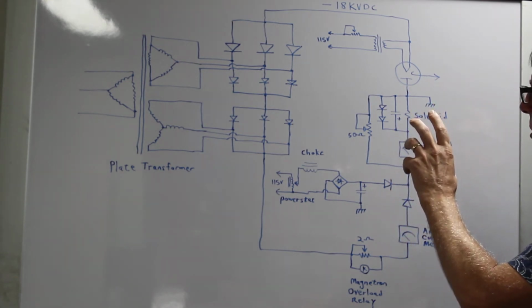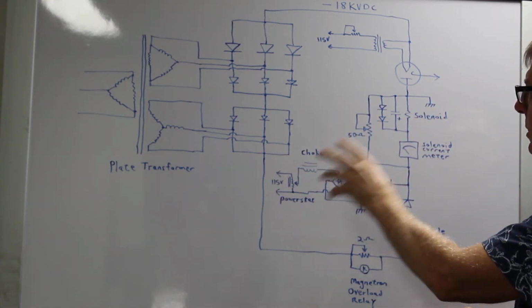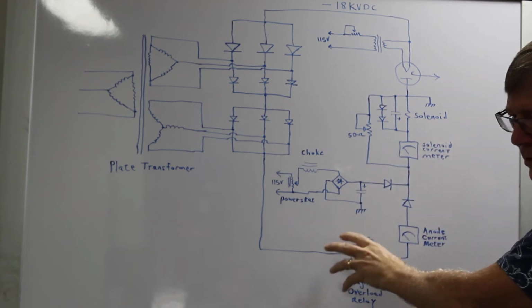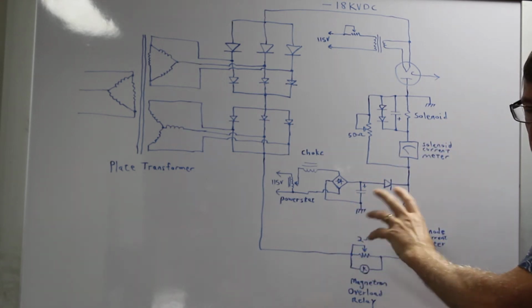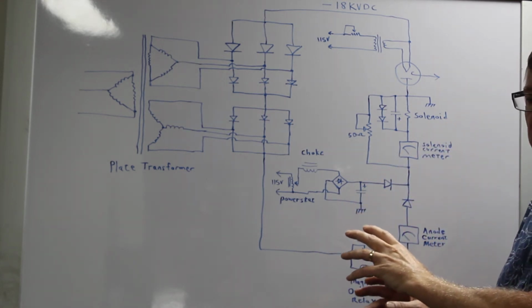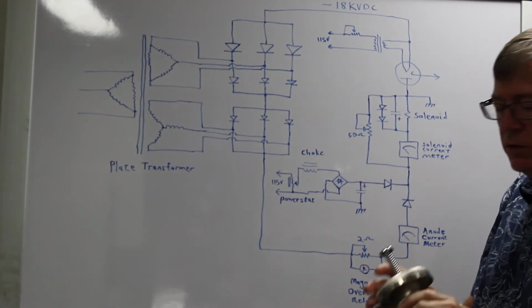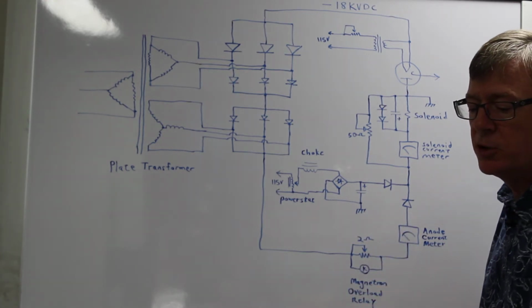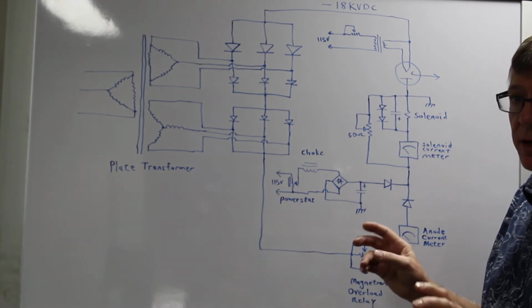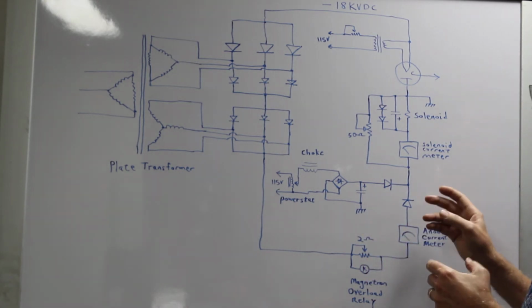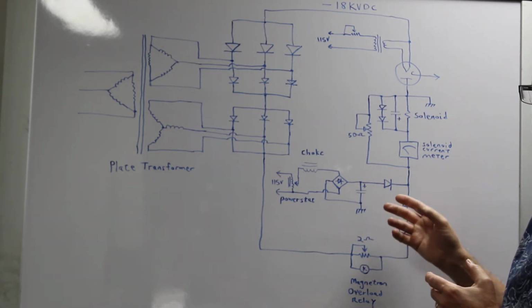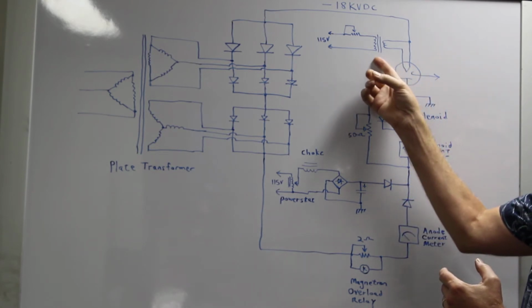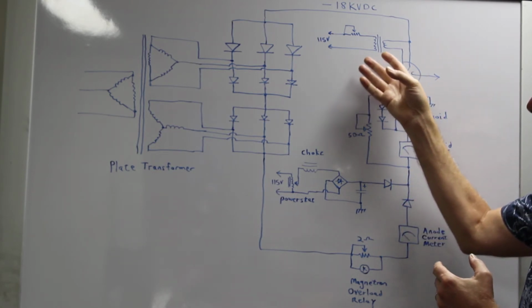So the combination of the anode supply, the filament supply, and the power stat, or the solenoid supply, is how we control the tube. The filament has to be at 2100 degrees to get the proper emission, and in standby, when we're not radiating any RF, that's 115 amps at approximately 12 volts. That's derived here.